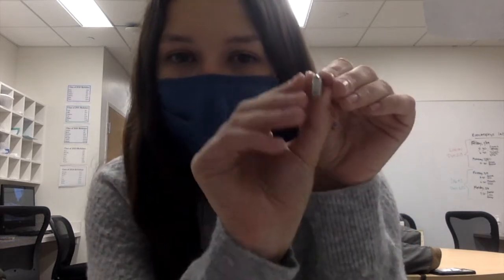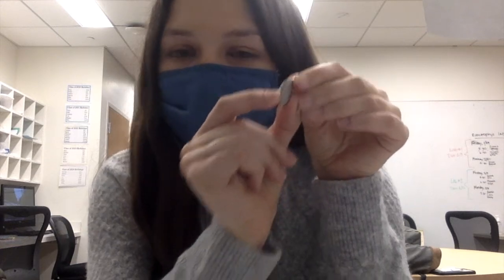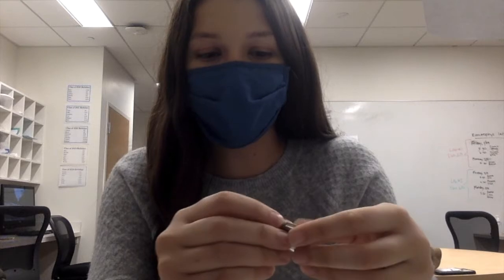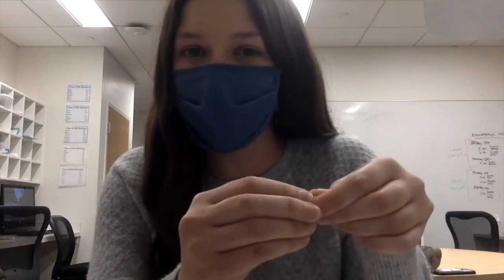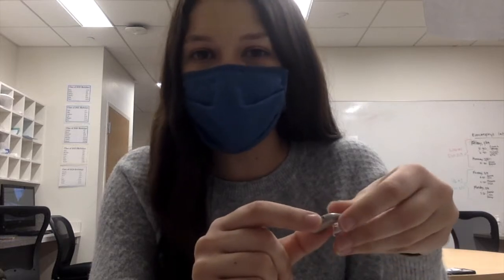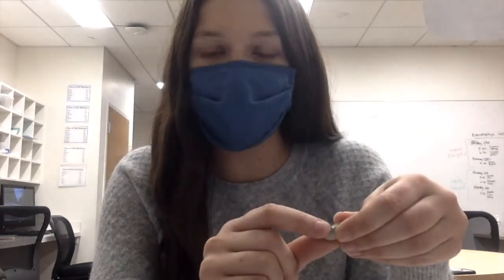Some hearing aids don't have a battery like we just talked about. They're rechargeable hearing aids. So if you wanted to turn those hearing aids on or off, there's a button on the back of the hearing aid right here, and you hold the button down and listen, and it'll start beeping when it turns off. So if you're not able to open the battery door, push and hold the button, and that'll turn the hearing aid off. Once you don't hear any sound coming out of it, push and hold the button again, and that will turn the hearing aid back on.